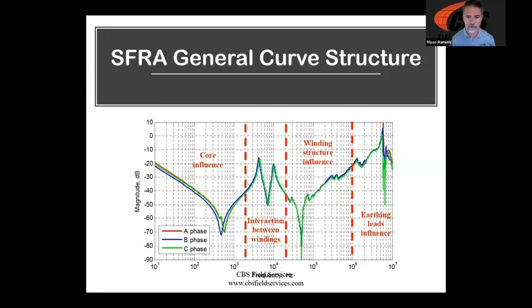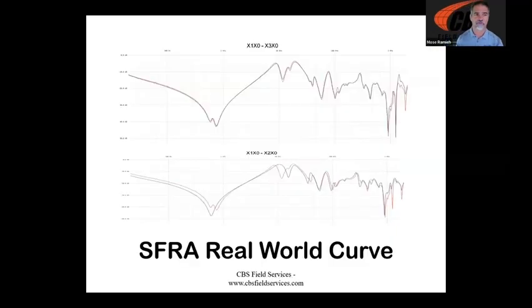So let's talk about what that might look like in the real world and where we might see some differences. And so here's some recent testing that we did. And we'll note here that we have X1 and X3, and you'll notice how perfectly aligned these two curves are, right? From start to finish, they're in great alignment. But when I compare X1 to X2, you'll notice in the core influence area, as well as the winding to winding area, you can see that there's a shift between these items. So once again, this is a transformer that's never had an SFRA conducted on it before.